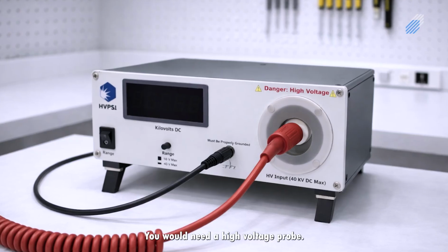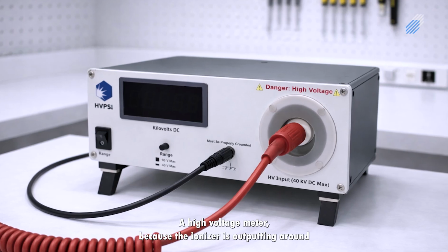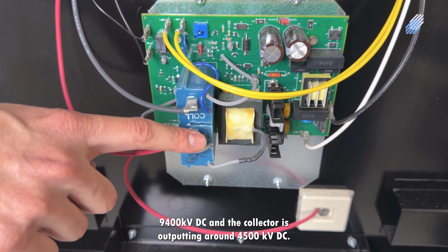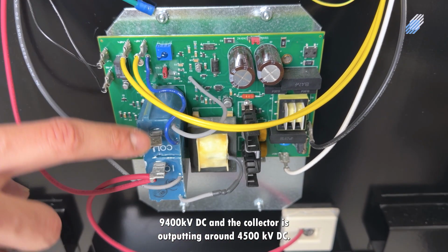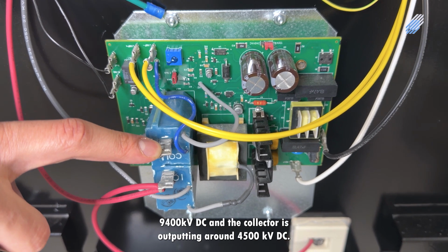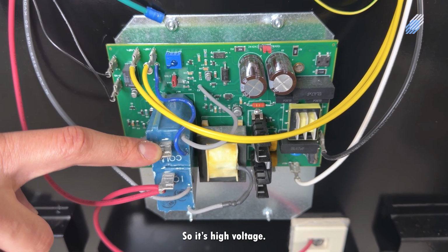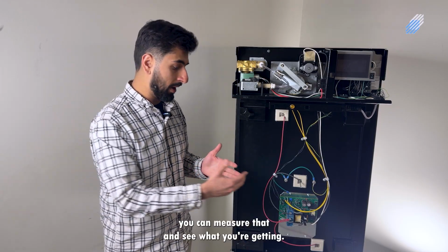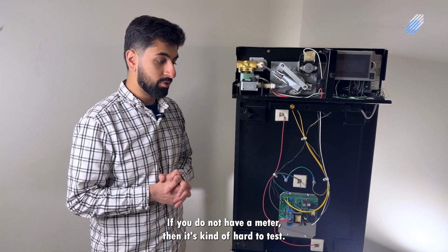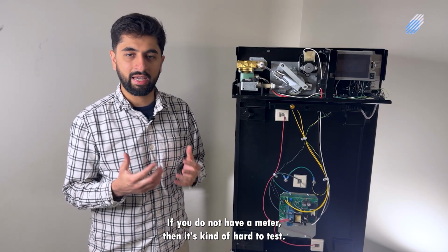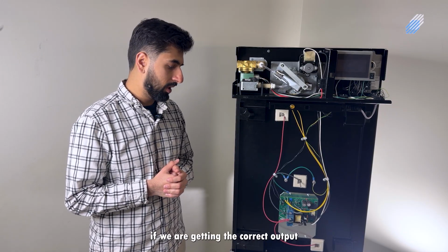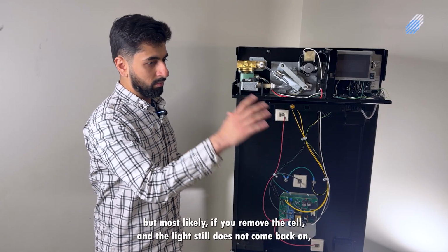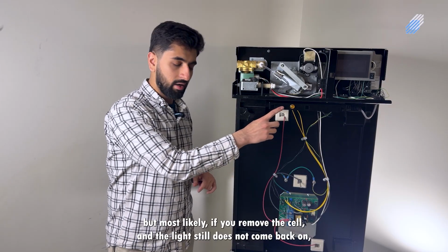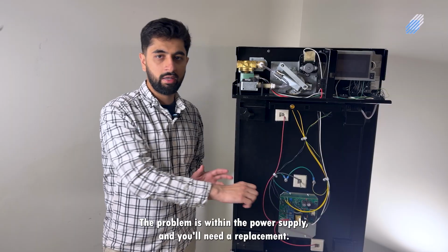You would need a high voltage probe, a high voltage meter, because the ionizer is outputting around 9,400 volts DC, and the collector is outputting around 4,500 volts DC. So it's high voltage. If you do have a high voltage meter, you can measure that and see what you're getting. If you do not have a meter, then it's kind of hard to test if we're getting the correct output. But most likely, if you remove the cell and the light still does not come back on, the problem is within the power supply and you'll need a replacement.